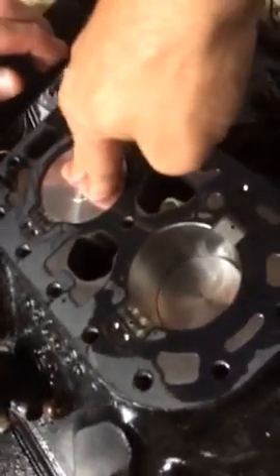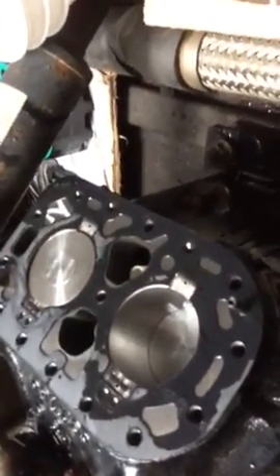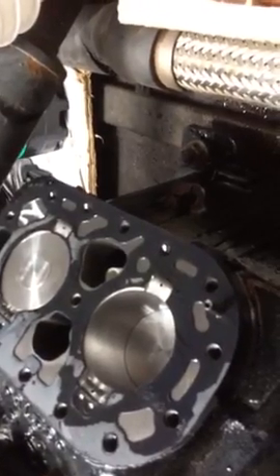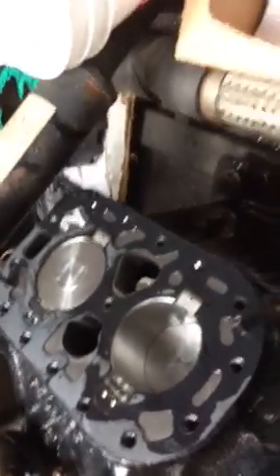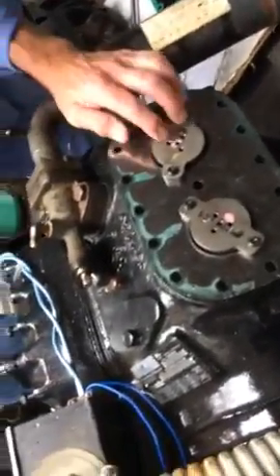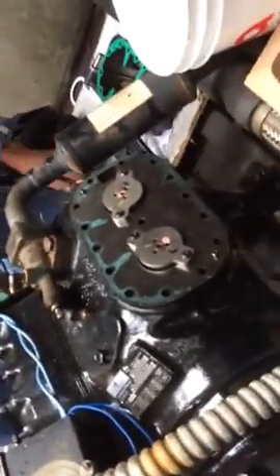It can't move anymore. No, it's at the top dead center — sometimes it takes a while. That was a lot of oil up there, though. That's the first thing that comes to mind. It could be because we were short-cycling it too, and it didn't have a chance to get going. A lot of times when you're short-cycling, that's how you get a lot of oil out in the system.